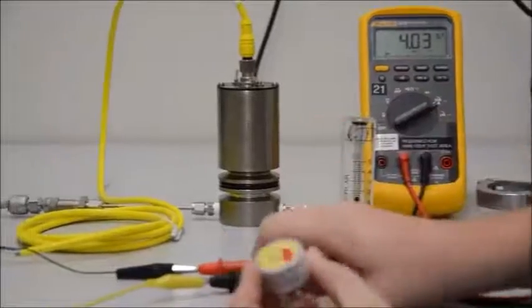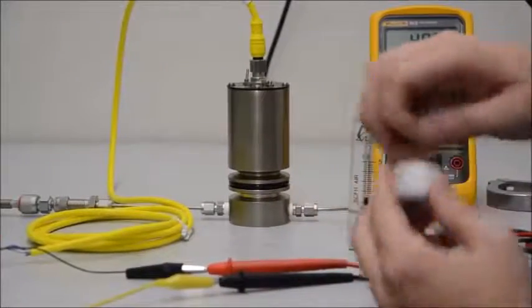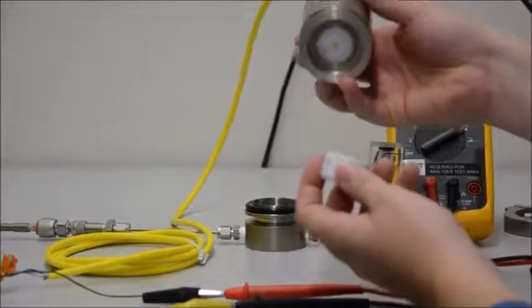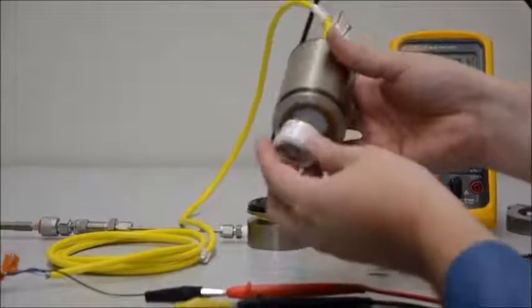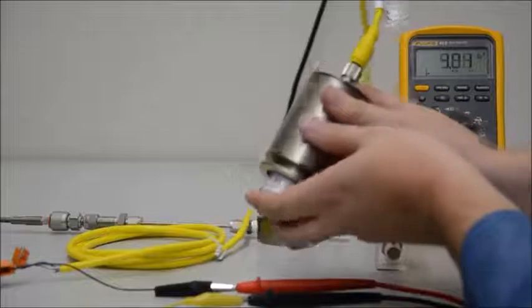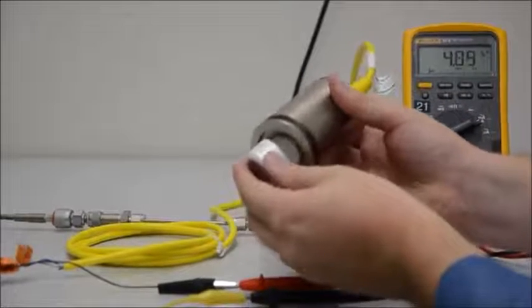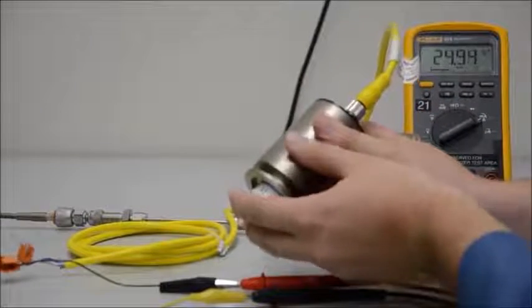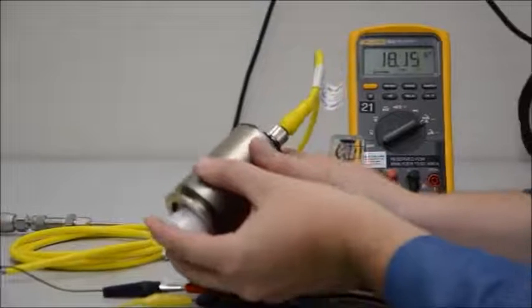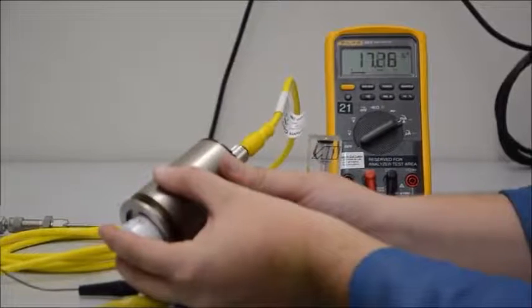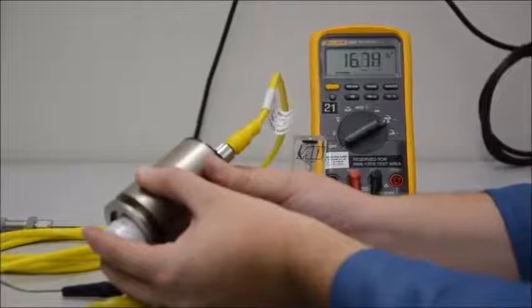remove the two shorting clips on top, and hold the gold side of the sensor to the gold pins at the bottom of the analyzer. We'll now see the reading on the multimeter change, and we're going to want to wait for that to settle.